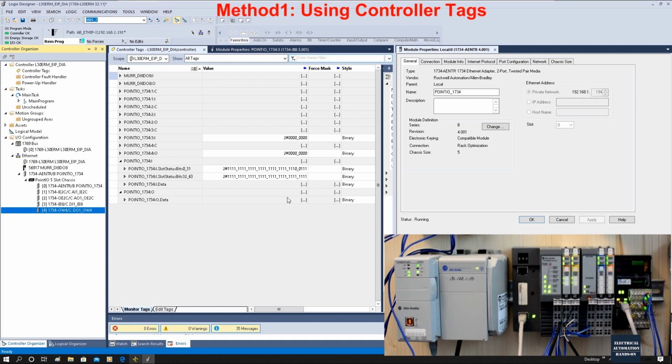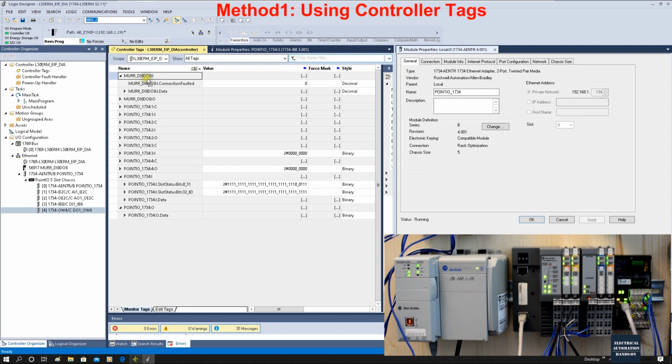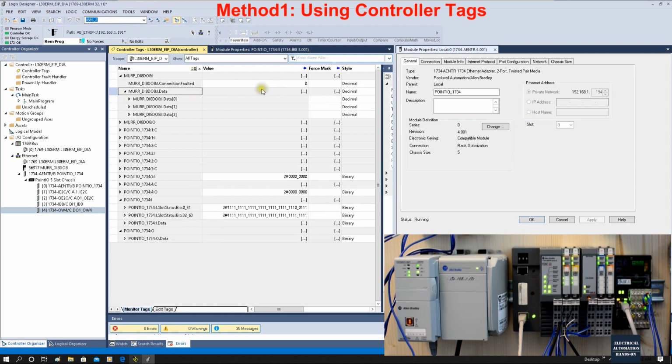Okay, all the connection returned. So as we can see, once it returns to the normal status, this is 0. Okay, this is the Point IO station using the slot status. And for the EDS file, we can go to the station, and basically the EDS file will come with this connection faulted status. So when it's normal, this bool is a 0.